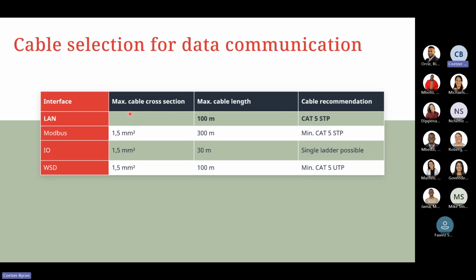For Modbus, your max cable cross section is 1.5 mm squared. This is why we typically recommend using twisted pairs for the Modbus RTU communication side, and you've got a max cable length of 300 meters from the device to the inverter itself. So if you've got a smart meter in the field, 300 meters from the inverter is the maximum length we can have the smart meter located. Again, using Cat5 STP cable, again using twisted pairs.